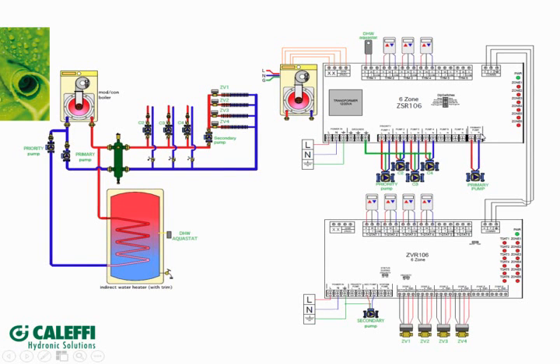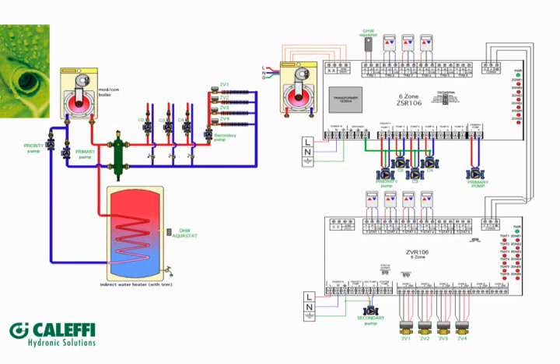XX contacts close, so the boiler fires, and our primary pump in this case would fire. So it knows there's a heat demand, and you'd be able to supply those zones out there with heat. And then the key is that secondary pump over on the very far right has to go to the second, right? Yep, to that board. That's correct. Yep, it has to get wired to that secondary board. And if there's a priority call, this board will communicate over to this board, and it will hold off all of these zone valves, and the secondary pump will not run when there's a priority call over here. So this is a true possibility.